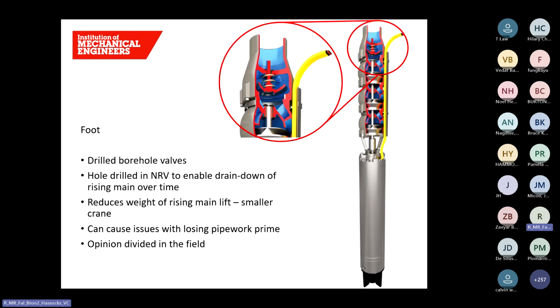The foot valve, when used on a borehole pump, can be drilled, which means that a small hole is drilled in the valve and allows water to drain back during maintenance. The reason for this is because borehole pumps tend to have long rising pipes, which when full of water can be very heavy. So as the pump is lifted from the well, water can drain out and reduce the weight.